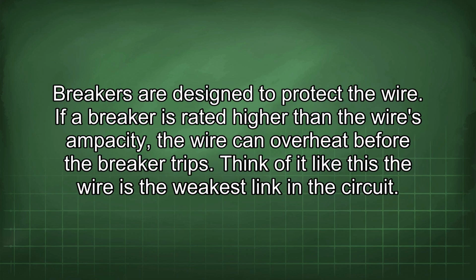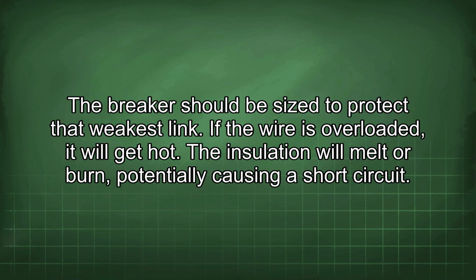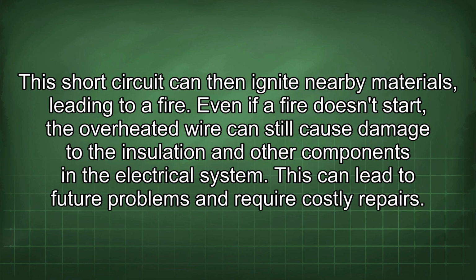Breakers are designed to protect the wire. If a breaker is rated higher than the wire's ampacity, the wire can overheat before the breaker trips. Think of it like this: the wire is the weakest link in the circuit. The breaker should be sized to protect that weakest link. If the wire is overloaded, it will get hot. The insulation will melt or burn, potentially causing a short circuit. This short circuit can then ignite nearby materials, leading to a fire.